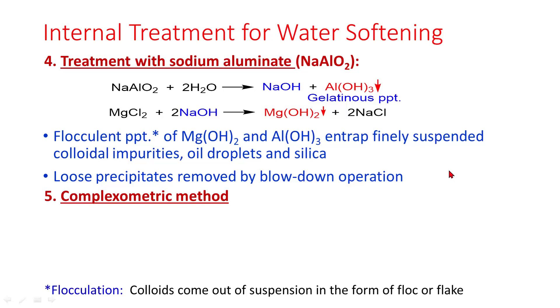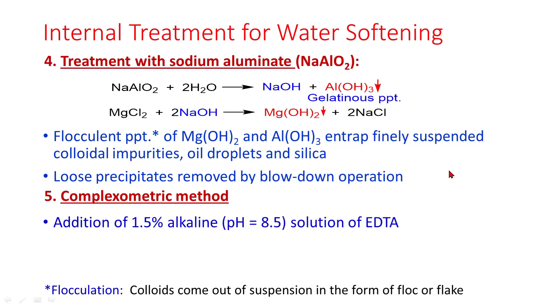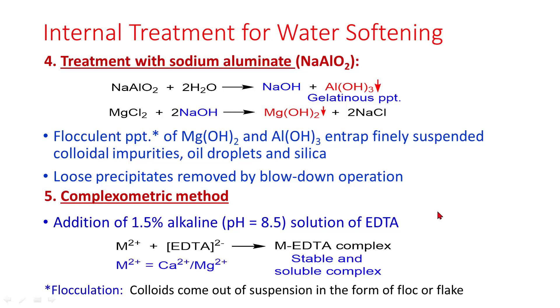In the complexometric method, a 1.5% alkaline solution of EDTA at pH 8.5 is added. Calcium or magnesium ions with EDTA form a stable, water-soluble calcium-magnesium EDTA complex. Hence it does not create a problem as far as scale and sludge formation is concerned.